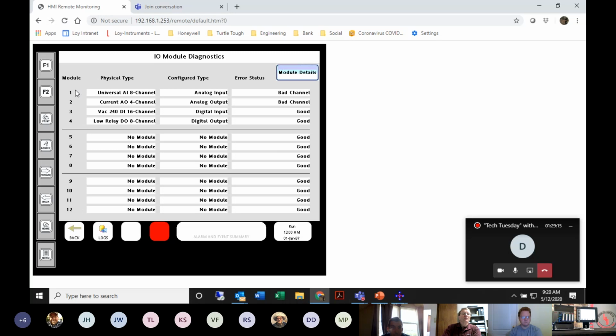Now it'll tell me in my 4-slot rack, where I have modules 1 through 4, what each one of those cards is physically. I have an analog input in the 1st slot, an analog output in the 2nd, a digital input in the 3rd, and a relay output in the 4th. On my analog input and my analog output, it's indicating I have bad channels. Typically, when it says this, it means that I do not have a thermocouple, or I might have a sensor that has failed open, on my analog input.